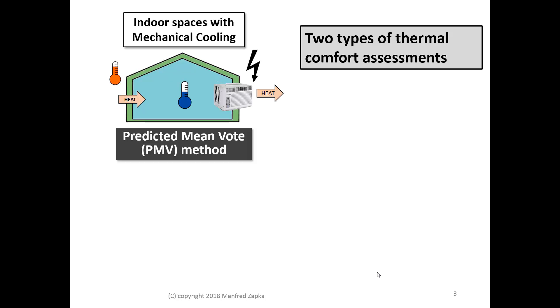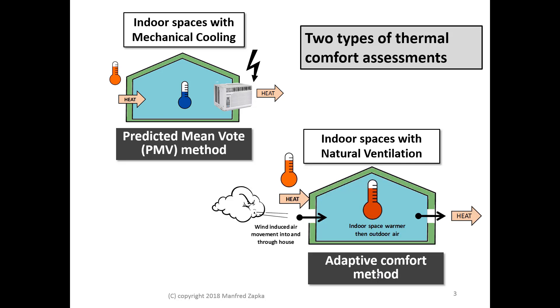ASHRAE 55 standard uses two types of thermal comfort assessment. One is for indoor spaces with mechanical cooling — wherever we have an AC installed — and here we use the method of Predicted Mean Vote, PMV. The other thermal comfort assessment is for indoor spaces with natural ventilation where we do not have mechanical cooling, and here we use the so-called adaptive comfort method.